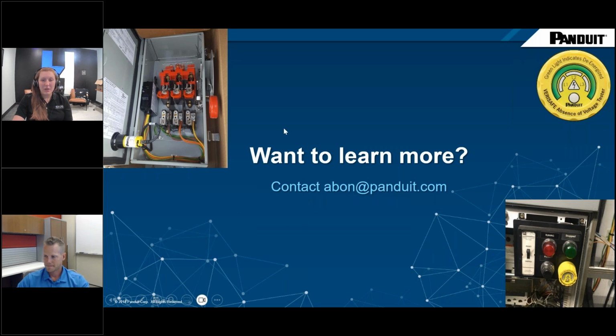Definitely gave us a better look at not just indicator lights, what they do versus test ports, and then actually what it takes to get the rating as an absence of voltage tester. And it really does save a lot of time, but it also saves your chances of exposure. Those stories of people that get in and, oh, it actually is still energized. Well, you're not going to be surprised. You'll know ahead of time.